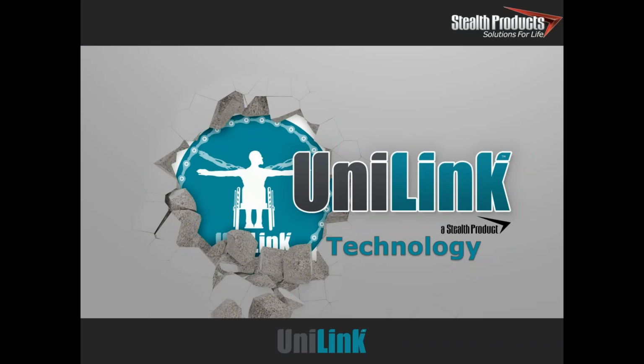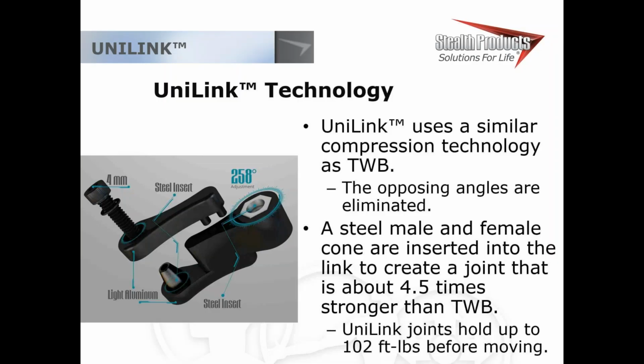UniLink is our answer to all of this. So UniLink is going to use a very similar technology as TWB. There's still no teeth, and it's still a compression fitting. This time we eliminate those opposing angles and kind of take away room for error. The only way you can really mess up tightening and loosening these joints now is just not tightening it enough.